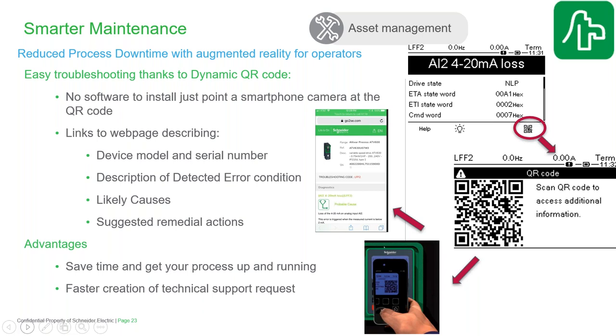In addition, it describes the error condition that's active, the likely causes that made that error condition occur, and some suggestions on what actions you should take to fix it so you can get your equipment running again. You can also access documentation from that page, so you get the manuals, the wiring diagrams, and all that information is available as well. That helps the operator on the site sort out what the problem is and get the problem fixed and the irrigation pump back running and providing service again.